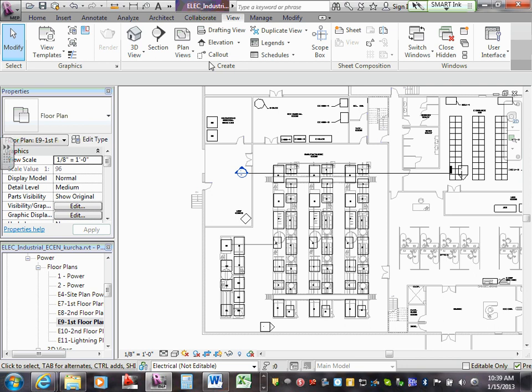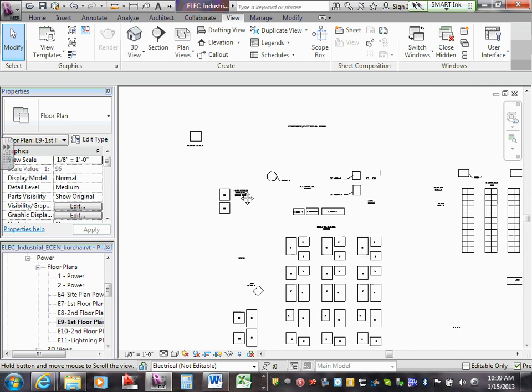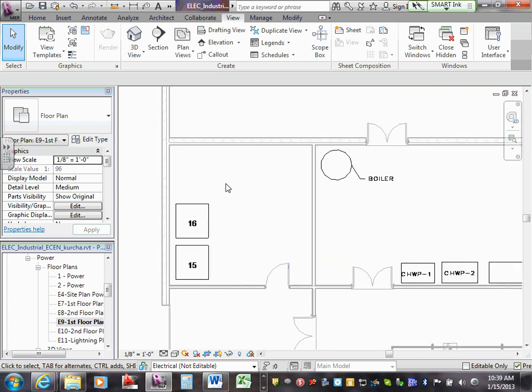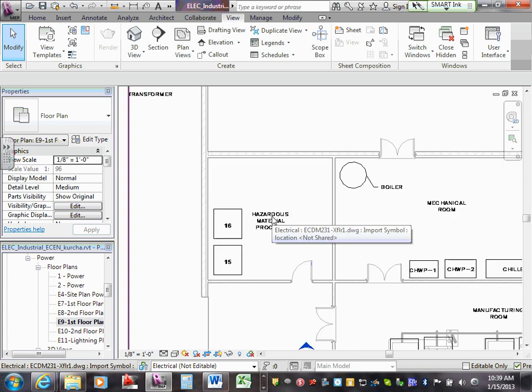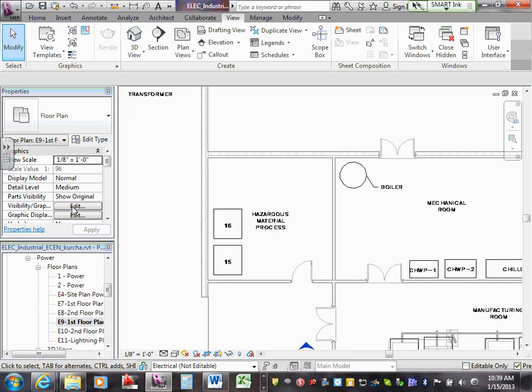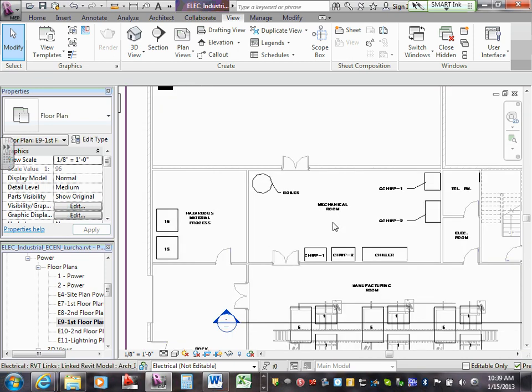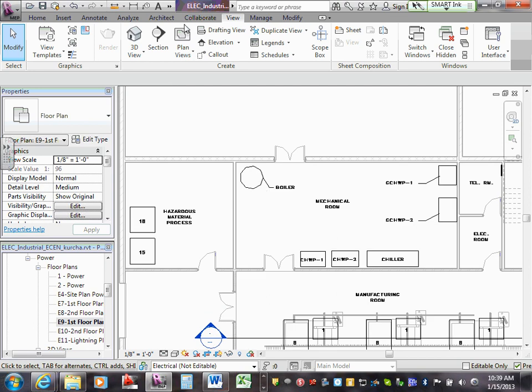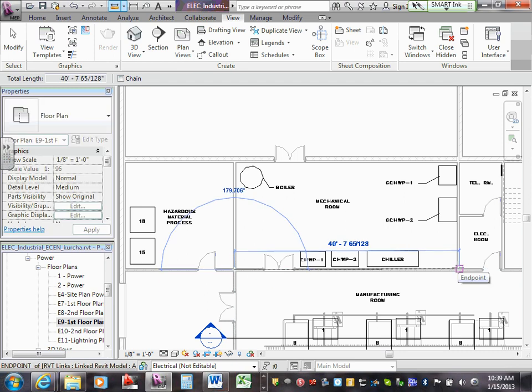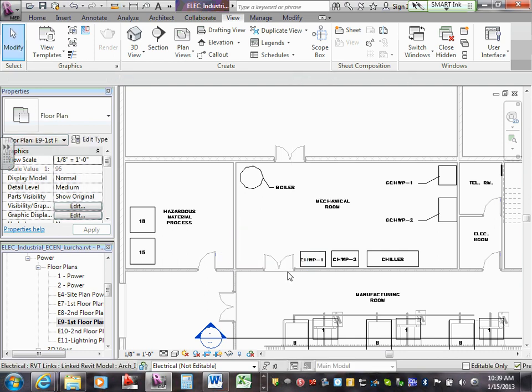And once again, in this area, we have a Class 1, Div 1 hazardous area. You've got the beacon strobe, which is typically yellow, and the horn. One more: you're gonna have a horn strobe in the mechanical room. They might have one on each side, depending on how much equipment's in here, so that anybody who's working in here can see one side flashing, because they're probably not gonna be able to hear in there, but they like to have some kind of visual indication that something's going on. If you've got one of your maintenance guys working on a chiller unit in there, they'll be able to see something.